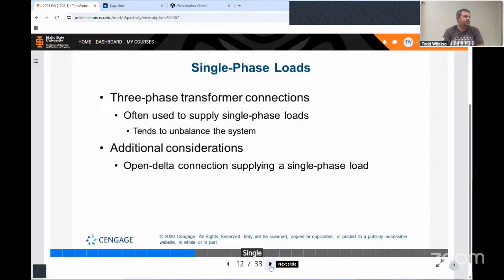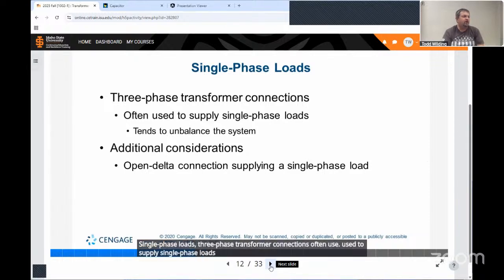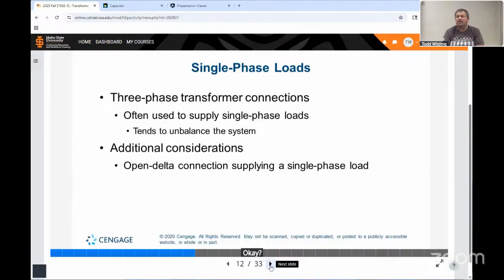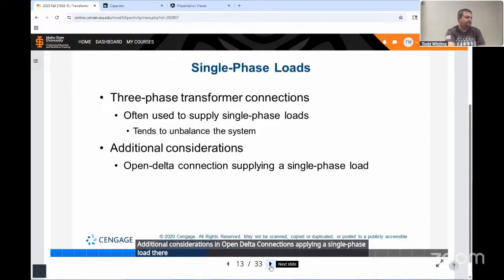Single phase loads, 3-phase transformer connections often used to supply single phase loads, tends to unbalance the system. Okay, you do not see that a lot, but if you do, you're going to have an unbalanced system, and you will have unbalanced loads on a Y system if you're not careful. Additional considerations, an open delta connection supplying a single phase load there as well.